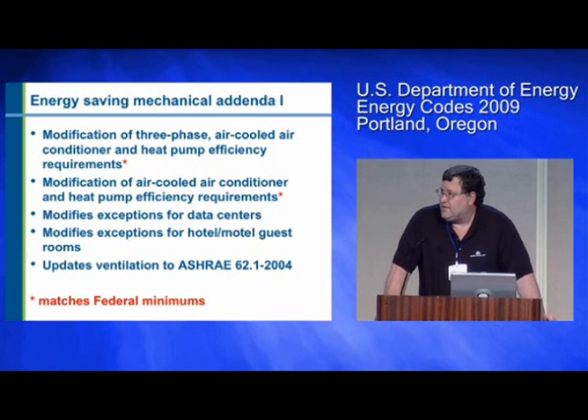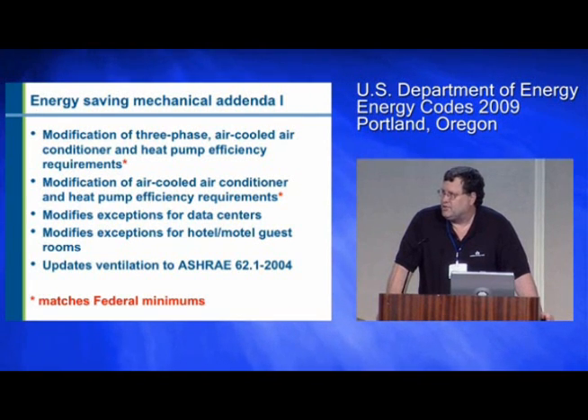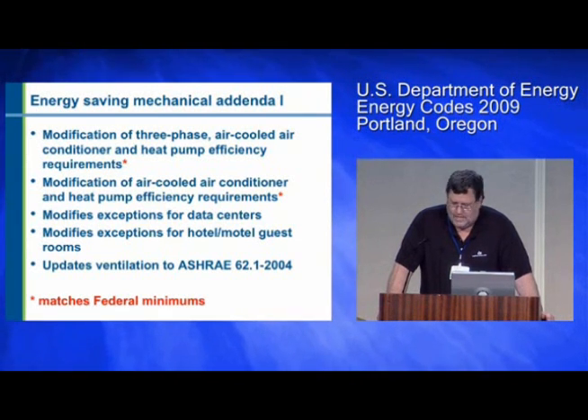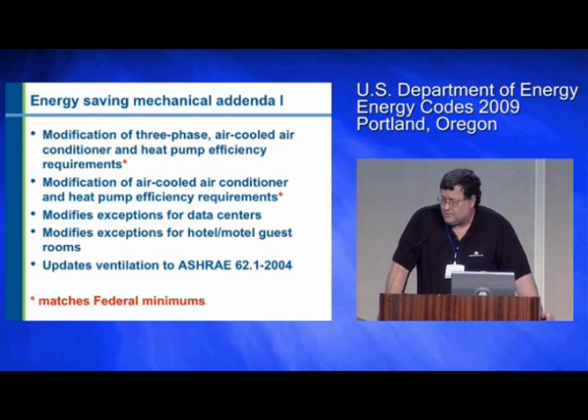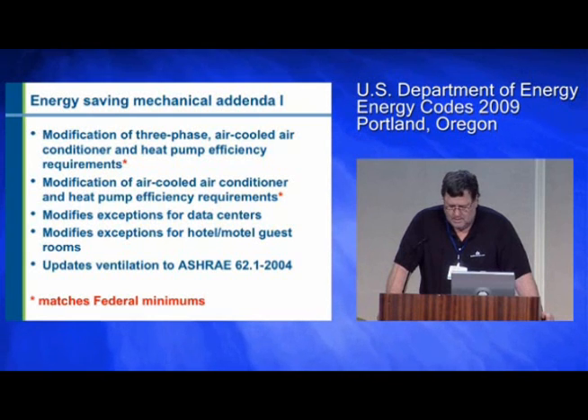There has been a number of changes to how data centers are treated in standard 90.1. They used to have a couple of special exceptions just for data centers. Some of those exceptions have been removed. ASHRAE got a lot of evidence that the data centers didn't need quite the tight control of the temperature that everybody has always thought that they do need, and so they removed the exceptions. That's going to save energy. They've changed some of the requirements for hotel motel guest rooms, meaning there'll be a little more control of those systems. And they've changed the ventilation requirements in standard 90.1.